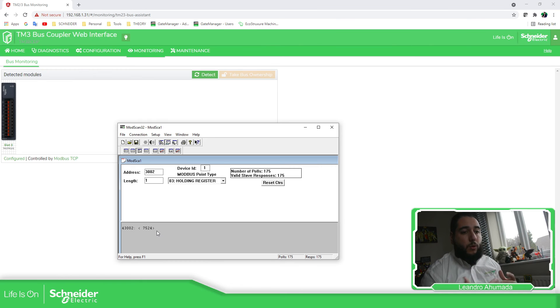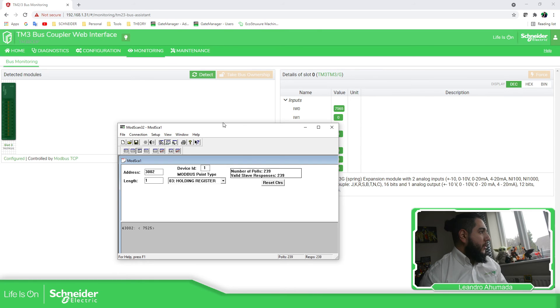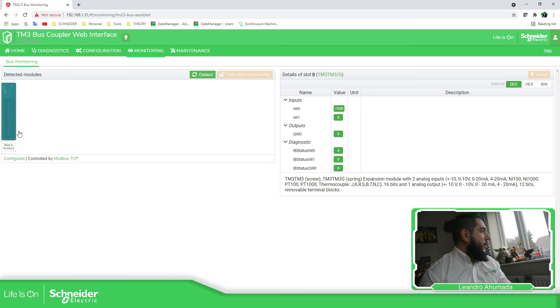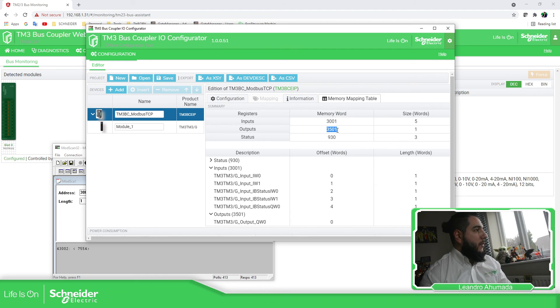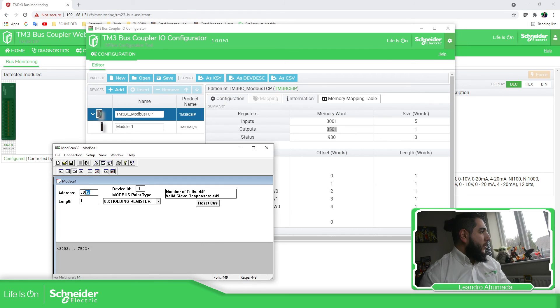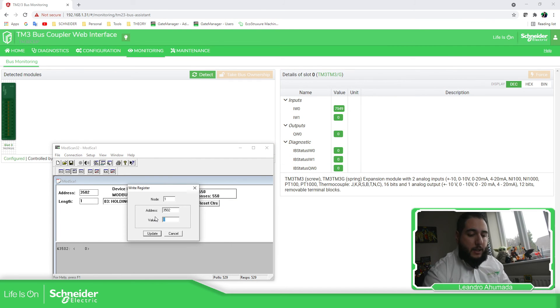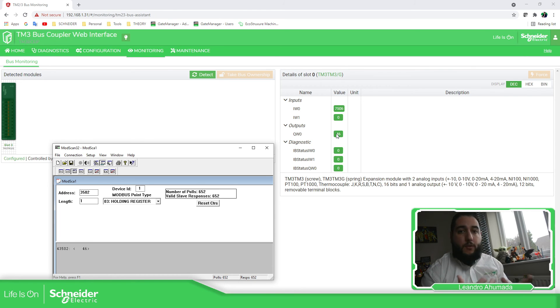This is how you can read the values. And if you want to modify the values, just connect again. You can see the values here. Now if I want to modify these values, what we need to do is to modify the output position. This position will start at 3501, so I need to add one — so 3502. This will be the holding register for the outputs. Now I should be able to change this value — I'll add 46 and update. You should be able to see 46 over there. This is how you can read and write information for the bus coupler.